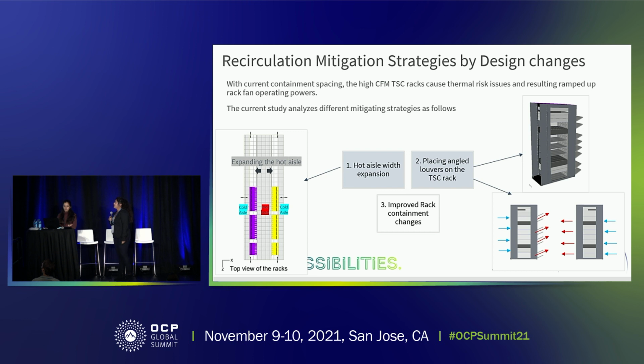So the mitigation strategies using design changes: one option would be to expand the hot aisle width in our data centers so that it would relieve some of the high hot aisle pressure that is accumulated in the aisles. And the other option would be to place angle louvers at the back of the high power racks so that some of the air, the high velocity jets, can now be deflected towards the ceiling instead of overflowing into the opposite rack. And the final one would be to actually improve the rack containment itself.